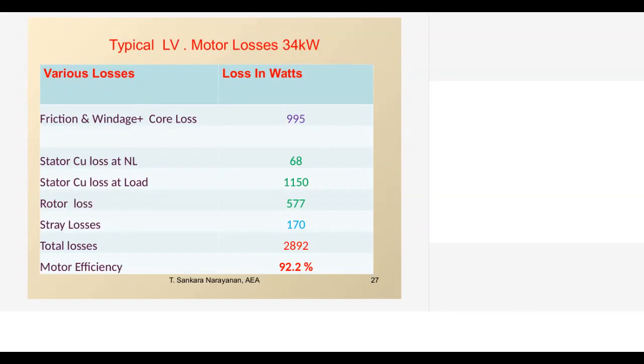Okay. See, basically, if you see a motor per se, here cut open is not there. A motor has a stator, and the stator has laminations. The stator laminations are stacked and varnish impregnated after the winding is done. So there is friction, windage and core loss. Here the friction losses and core loss will be less. Predominantly this is the iron loss in the motor.